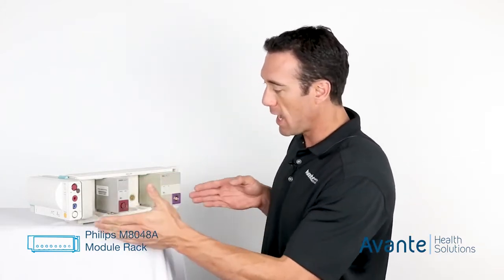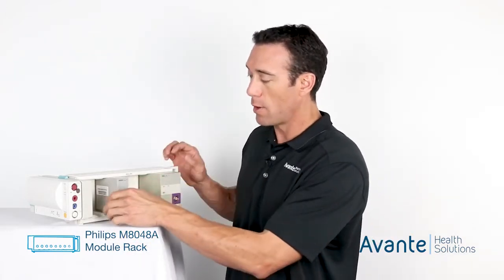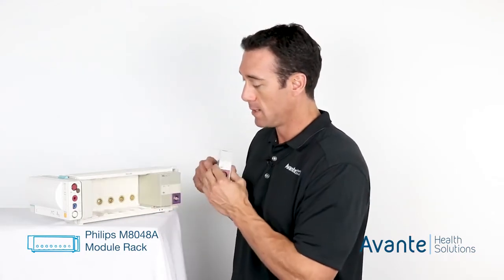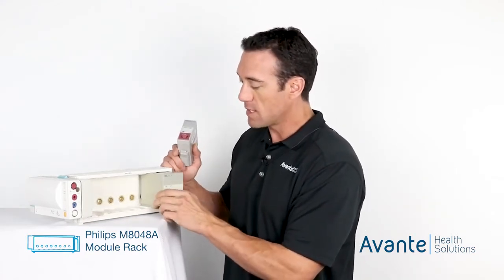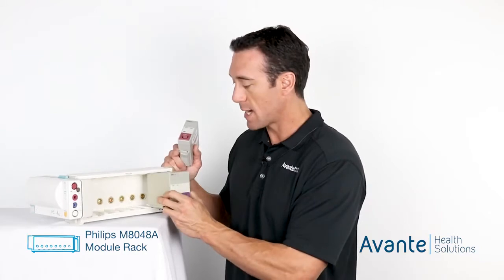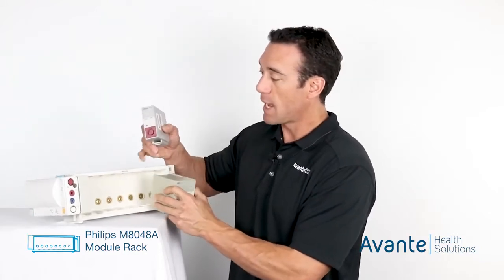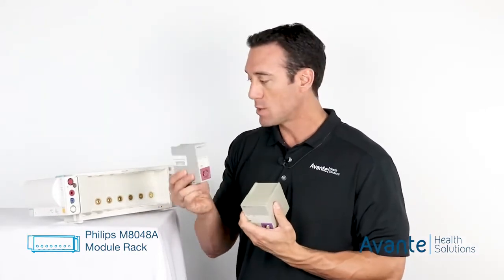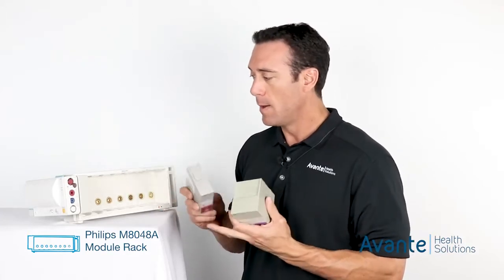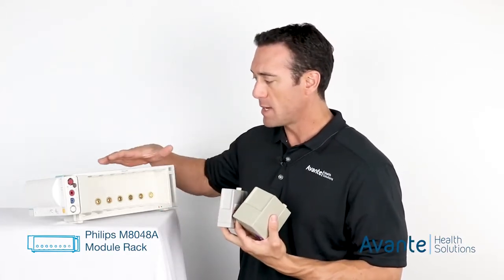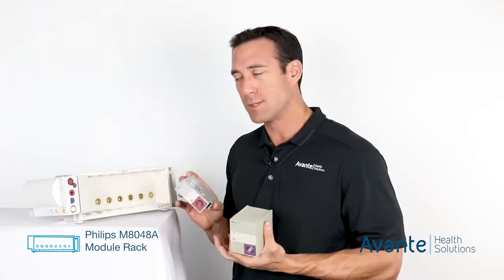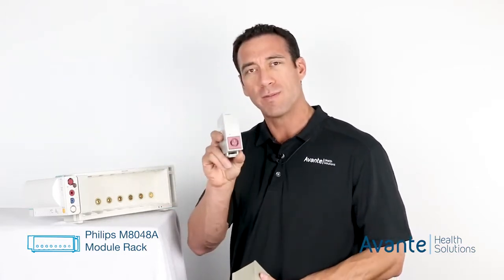We can put up to 8 expansion modules into the rack. Of course, if they're these 2x modules, that takes up 2 spaces, so that won't give us 8, but of the standard smaller singular ones, we can put 8 units in there. There are some limitations on how many of each type we can use with this rack — that information can be found in the service manuals or user manuals, so only a certain number of certain types of modules can be used at one time.